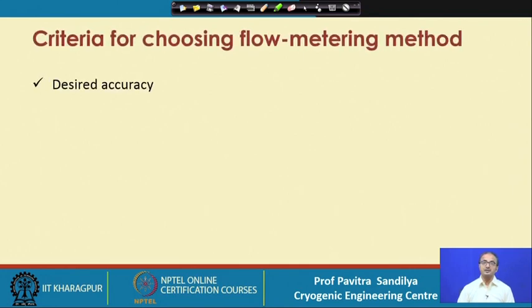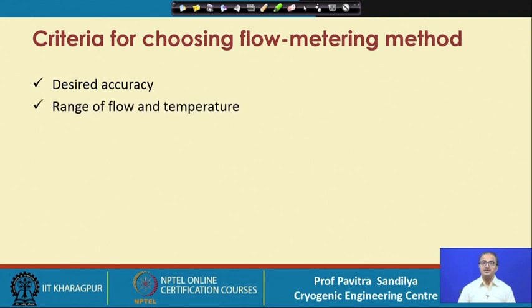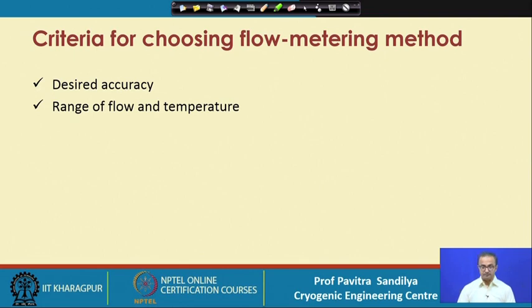What are the various criteria to choose a flow metering device? First is accuracy — there are many flow meters which will give different types of accuracy, so depending on the kind of use we shall decide how accurately we want to know the flow rate. Then the range of flow and temperature — for gas especially, temperature plays a role because it decides the density of the gas, and density changes the volumetric flow rate for a given mass flow rate. Then the type of fluid — whether we are handling liquid or gas — and the expected useful life, meaning how long the flow meter is intended to be used.